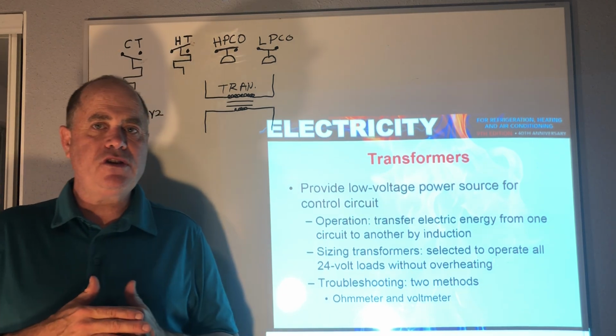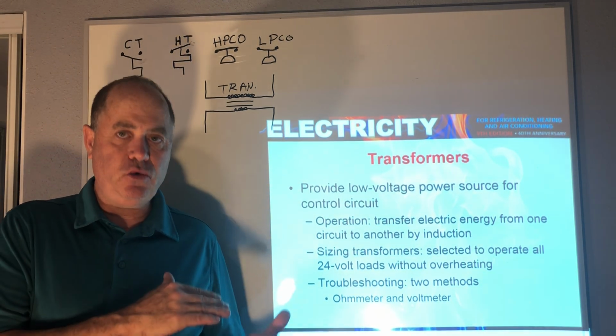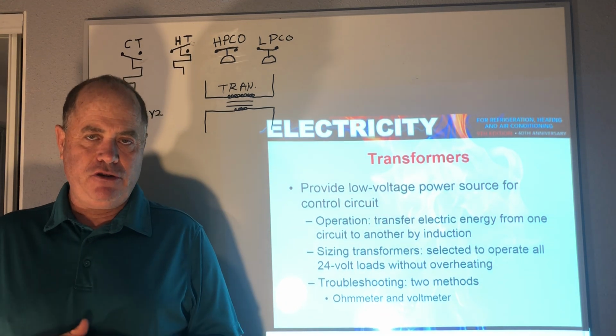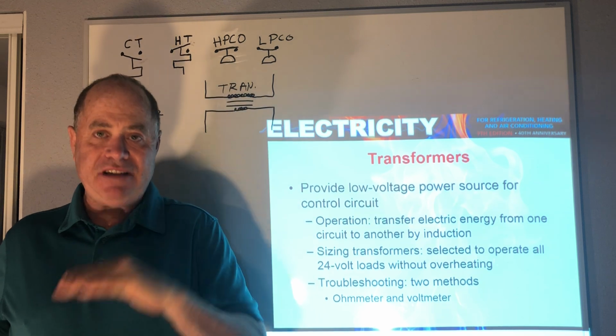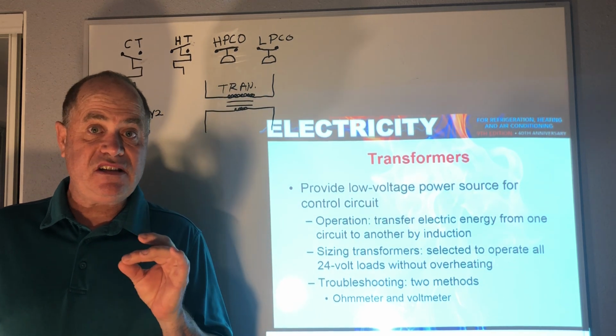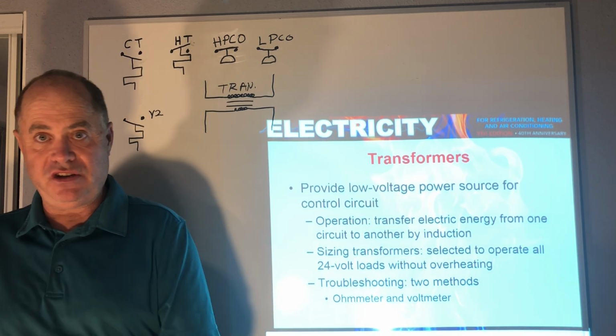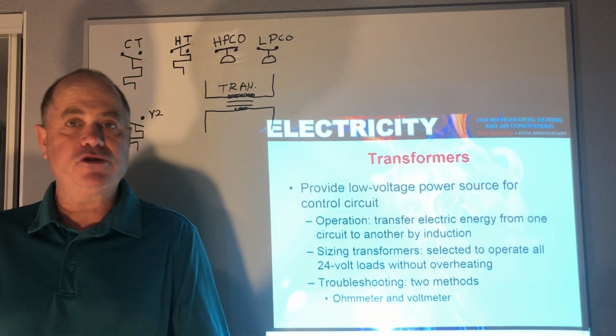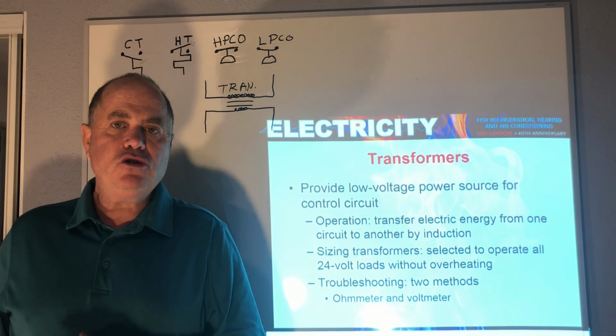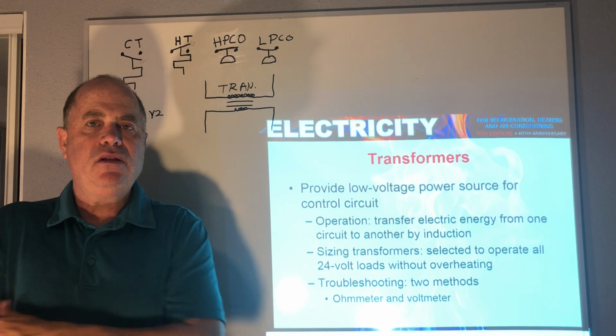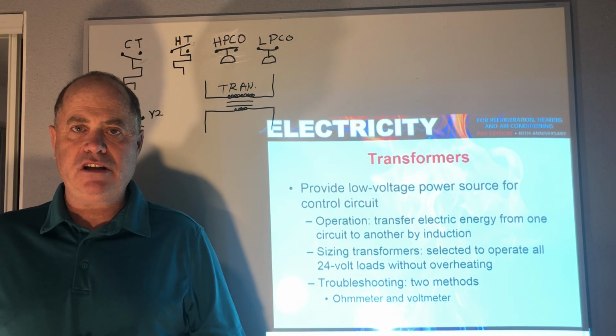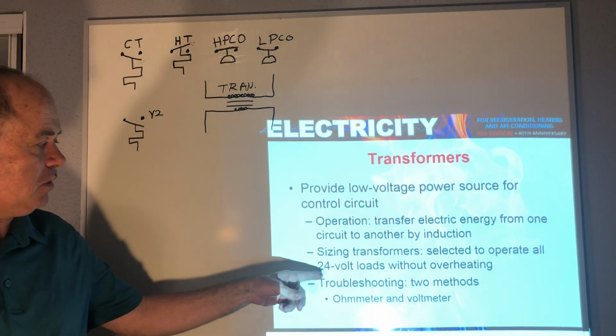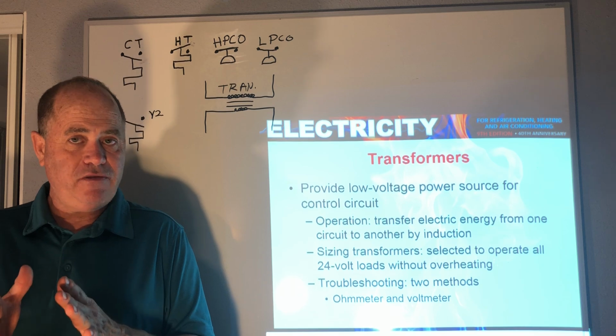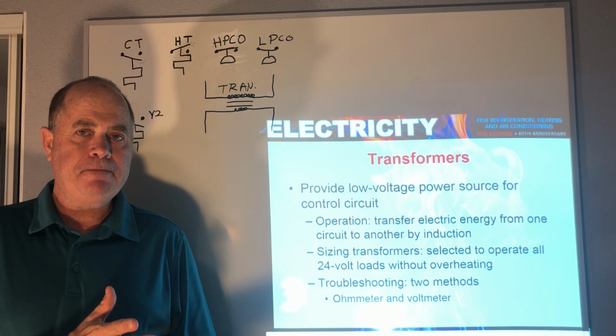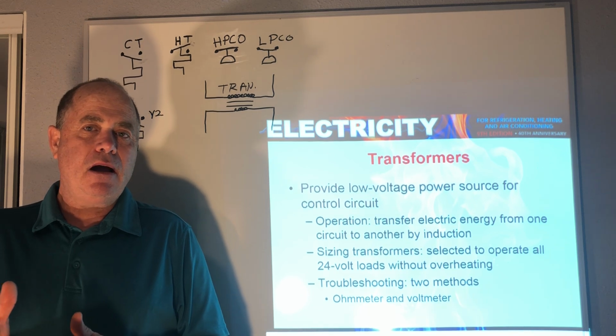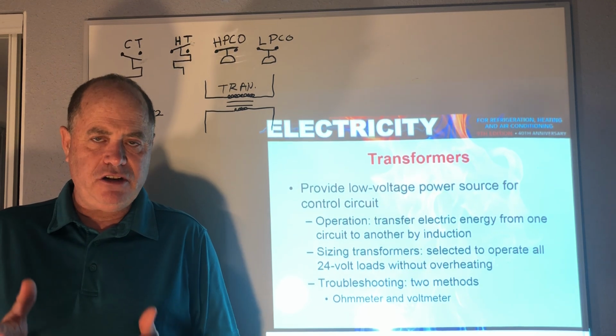Now, transformers are used to change one voltage into another voltage, and in the air conditioning refrigeration industry we're always just dealing with step down transformers, whether it's 4160 volts to 460 volts, or 460 volts to 230 volts, or 230 to 24 volts, or 230 to 115. And a lot of times inside air conditioning units, the voltage that we're creating with a transformer is quite commonly 24 volts, whether it's a package unit that takes 230 volts and drops it down through a transformer to 24 volts, or a split system that takes 115 volts and drops it down to 24 volts.